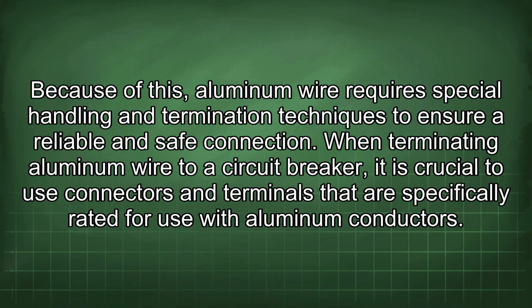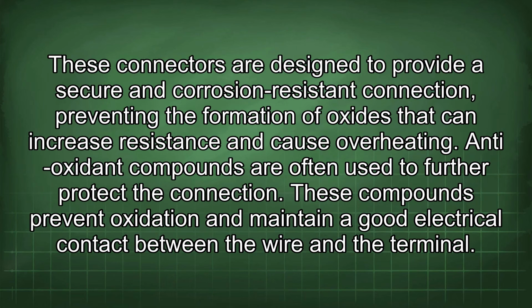When terminating aluminum wire to a circuit breaker, it is crucial to use connectors and terminals that are specifically rated for use with aluminum conductors. These connectors are designed to provide a secure and corrosion-resistant connection, preventing the formation of oxides that can increase resistance and cause overheating. Antioxidant compounds are often used to further protect the connection. These compounds prevent oxidation and maintain a good electrical contact between the wire and the terminal.